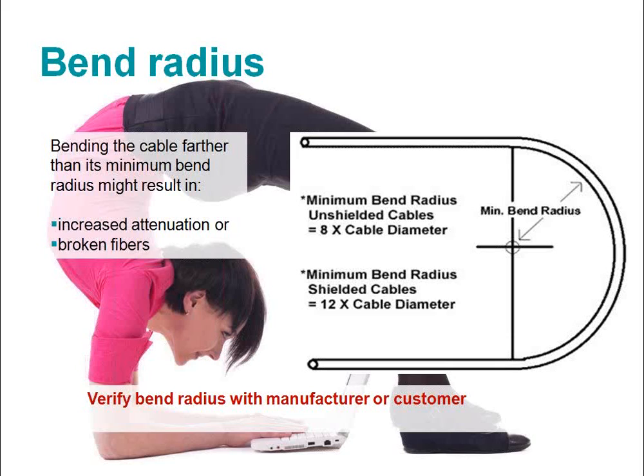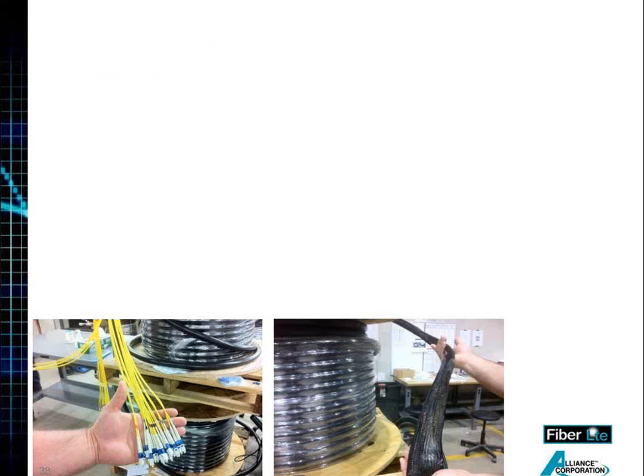When thinking about bend radius in a cable, you must look at the whole package. If we look at a composite or hybrid cable, with 6 conductors, 6 gauge, and subunits of fiber, that's going to be a rather large bend radius of about 20 inches. Whereas if we look at just a fiber-only cable, possibly armored, we're looking at a bend radius of about 5 inches. So when we look at the bend radius and at installing, always ensure that you know what these bend radii are.